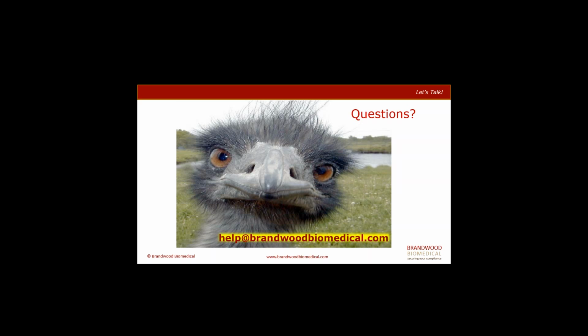And to get to design verification, your design controls are starting early, because to get to design verification you need those inputs. So to answer it, the design control process starts at the input stage.